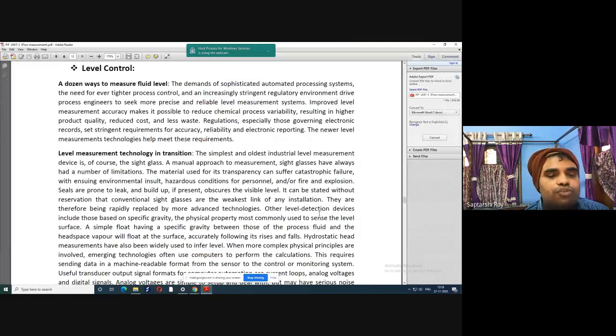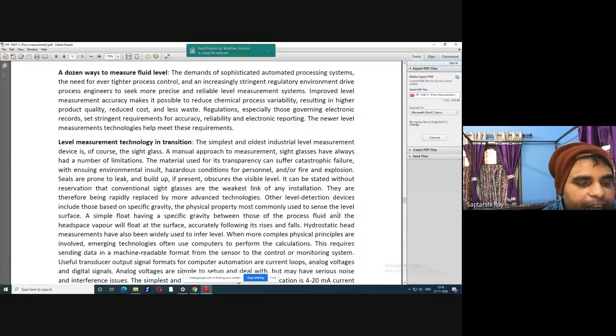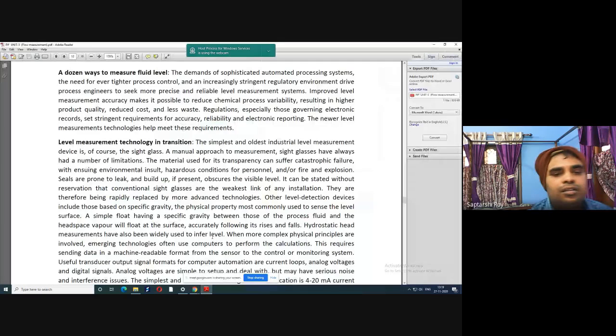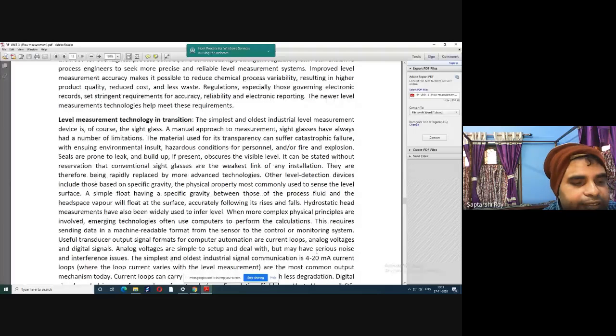Hydrostatic head measurements have also been widely used to infer level. When more complex physical principles are involved, emerging technologies often use computers to perform the calculations. This requires sending data in a machine-readable format from the sensor to the control or monitoring systems. Useful transducer output signal formats for computer automation are current loops, analog voltages, and digital signals.